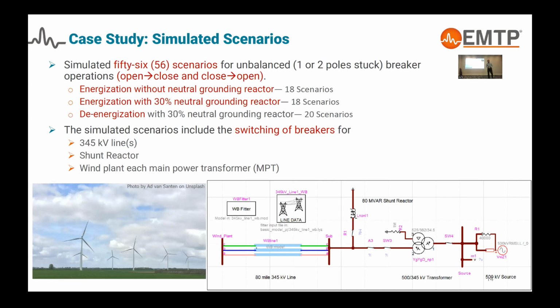Overall, we ran 56 different scenarios, which included single or two-pole unbalanced operation, not only for closing, but for opening as well. Those were related to switching of the breakers for the 345 kV line that you see over here, the shunt reactor breaker, and also the main power transformer of the wind plant that is not shown here. And 18 of those scenarios were the initial base scenarios in which we energize this line or different components, and we look at whether there is any zero sequence resonant condition or not. And we found that there was one case.